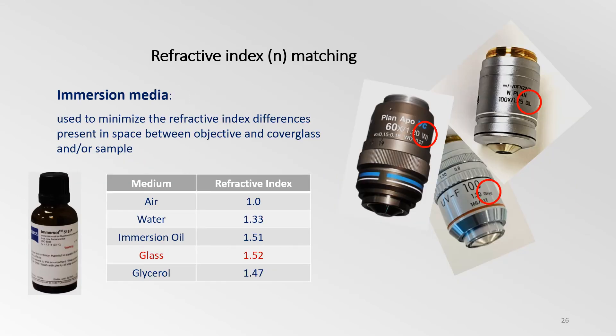Objectives that are designed to be used with oil, water, or glycerin increase the NA because refractive index differences between the objective lens and the cover glass or sample are largely minimized. Refractive index matching is an important factor to consider in optical microscopy, especially when working towards getting high resolution three-dimensional images.